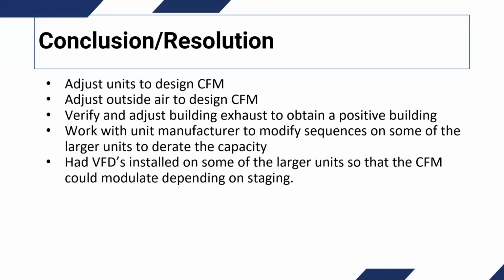And then on some of the units, there was no other choice besides having the manufacturer install some VFDs and modify the unit to where the fan would adjust depending on the staging. That way, if we had a 10-ton unit with two 5-ton compressors, we weren't delivering 4,000 CFM when we only had one 5-ton compressor running. And in this case, again, with the manufacturer's blessing, we reduced all the CFMs throughout the project to about 350 CFM a ton.